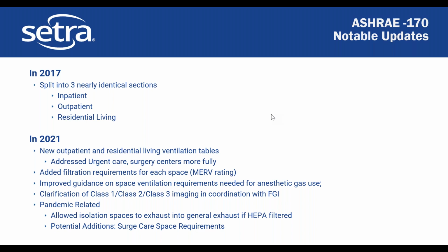They improved their guidance on anesthetic gas use. So what happened here was they had always assumed that anesthetic gas use required the maximum ventilation requirement. They recognize now that there's a number of other safeguards in place so that you do not actually have to have the full ventilation requirements, the maximum ACH, the full venting. So now you actually can do a little bit less, but still have anesthetic gas in use in a room.